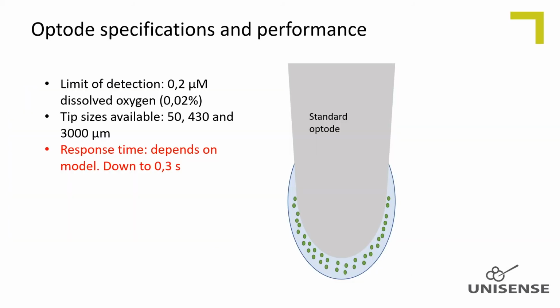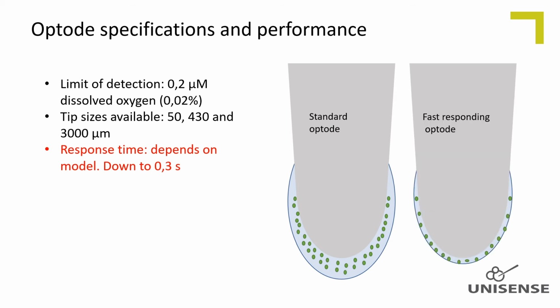The response time is a function of the time for obtaining partial pressure equilibrium between the sample and the polystyrene matrix. Thus, there is a trade-off between response time and lifetime. A thin polystyrene/dye matrix makes the optode fast responding, but as a consequence, the amount of dye is then limited, and therefore it will bleach faster compared to a slower responding optode with a thicker layer of polystyrene/dye matrix. So the response time is different for the different models. We can make them with a response time down to 0.3 seconds, whereas the large Optode 3000 has a response time of about 15 seconds.